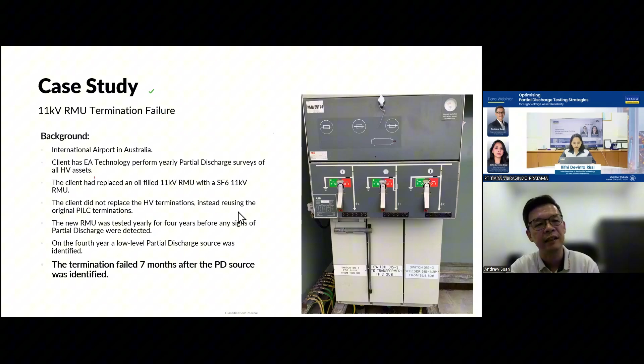So the new RMU was tested yearly for 4 years, no issue, new RMU, right? People say, oh, my asset is new, so it should not have a problem. So for the first 4 years, no problem. Okay, on the 4th year - still considered very new - we start detecting a low level PD source. And then from being detected to the thing failing, only 7 months. So this RMU failed within 7 months of detection.